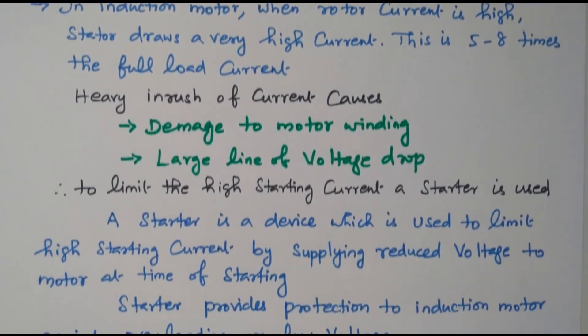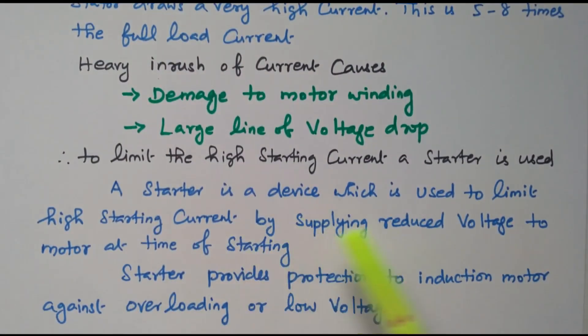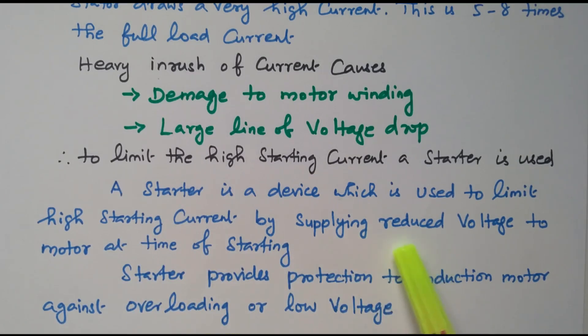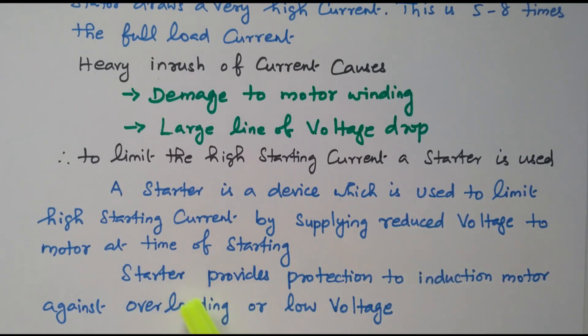A starter is a device which is used to limit the high starting current by supplying a reduced voltage to the motor at the time of starting. By supplying the reduced voltage, the current taken by the motor is automatically reduced. The starter also provides protection to the induction motor against overloading or low voltage.